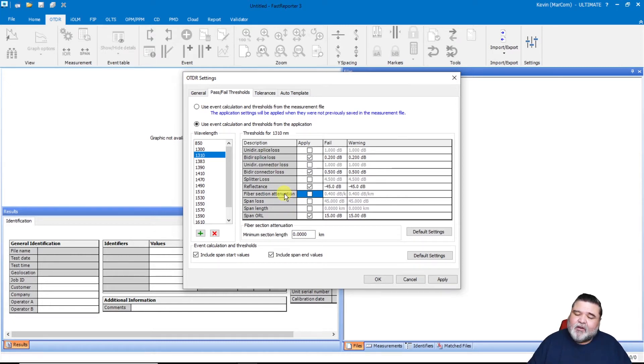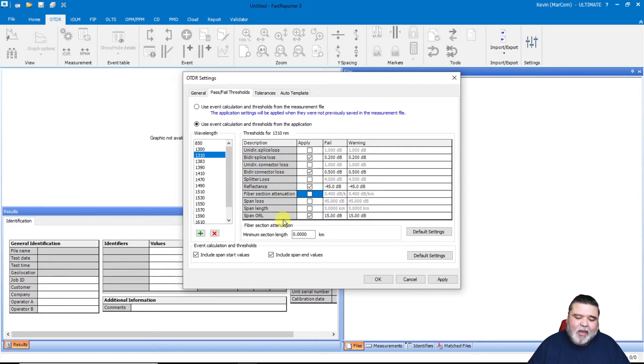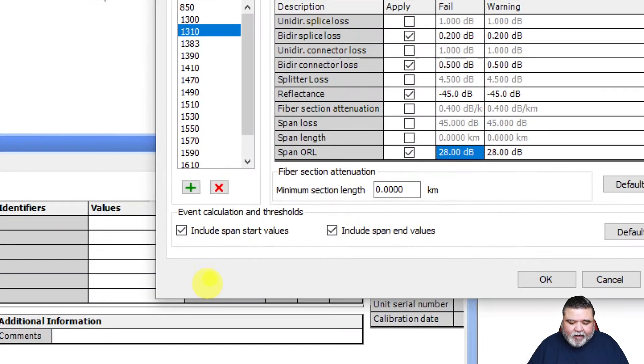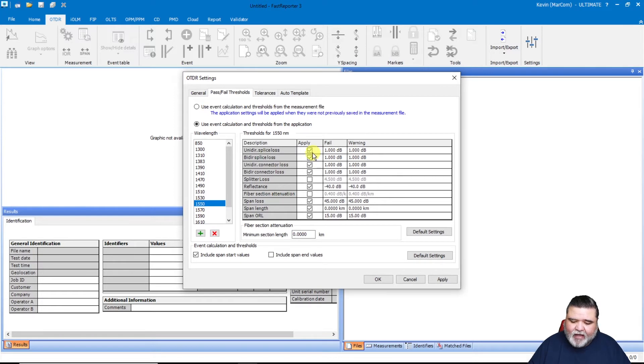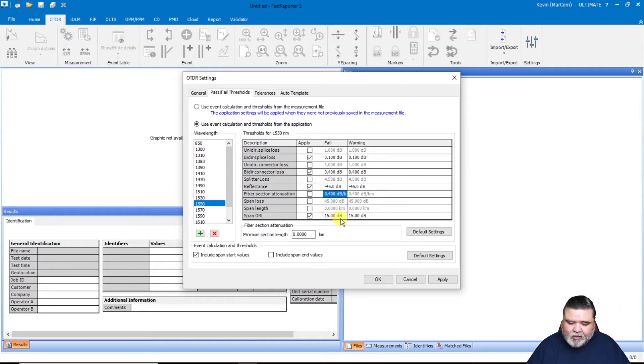I'm more concerned with fiber attenuation coefficient across the span. The fiber section attenuation is a valuable number, but I often turn it off if I'm expecting events very close together. I'll leave span ORL on and set it at 28 dB. All these values are set based on your organization's parameters. Down at the bottom, I have include span start and include span end. I do have a launch cable so I want to include the span start, but I don't have a receive cable so I uncheck include span end. Then I go to 1550 and do something similar — 1550 should have a lower value. The point here is to show you where you can set these values.